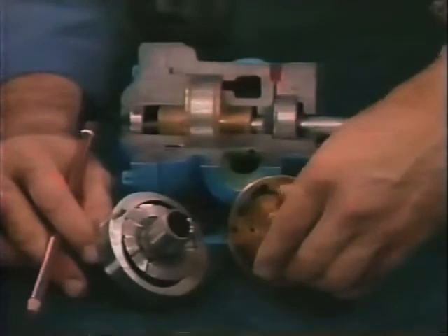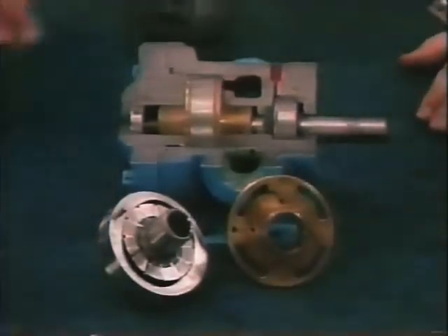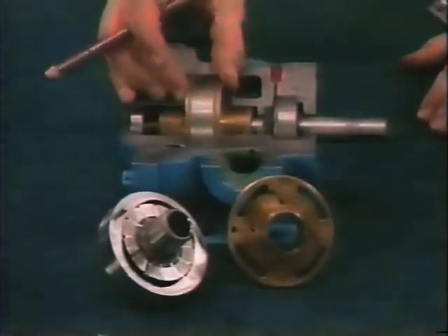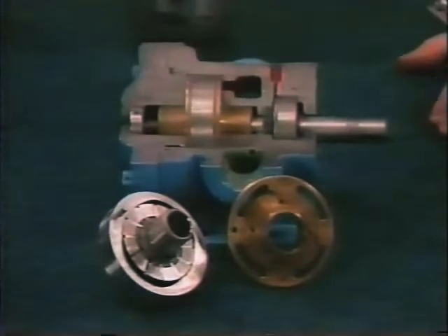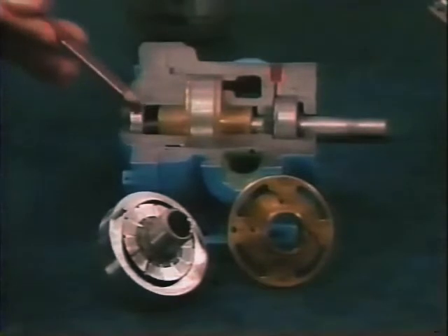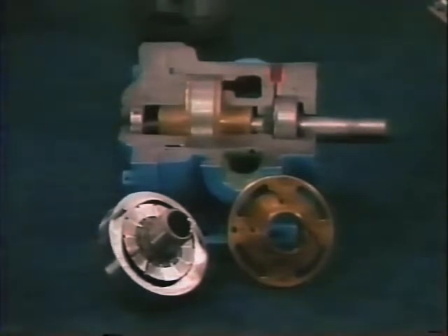ring, rotor, and vanes sandwiched between two bronze bushings, each containing two inlet and two outlet ports. Hubs on the rotor fit into supporting hubs in the bushings, which serve as bearings. The drive shaft only requires a small pilot bearing in the pump cover and a somewhat larger one at the front to accommodate any minimal side loading.